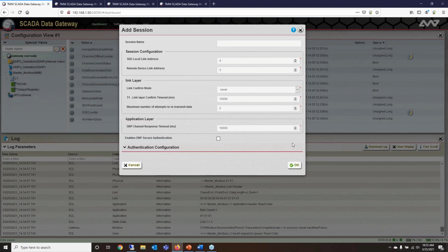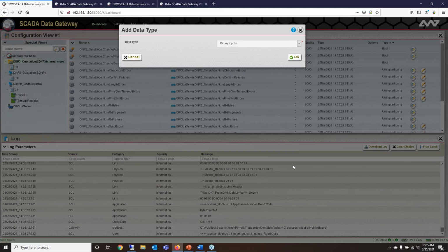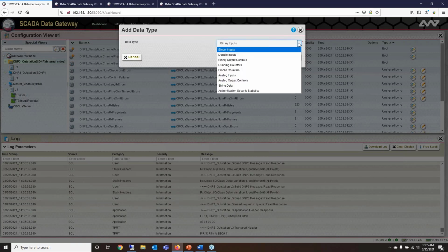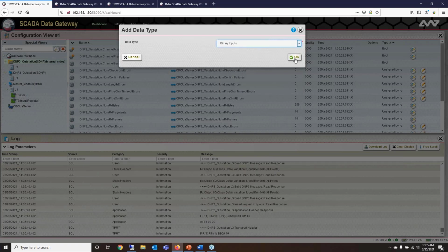And hit OK. You will see this looks a little bit different, and that's because we have chosen a DNP3 device this time rather than a Modbus. That being said, we still filled it with the defaults, and since my control center is also using the defaults, I don't have to swap anything here. So I'll just hit OK. And following the same logic as before, we need to give it a data type. These are obviously going to be different as well because we are in DNP3, but the comparable data type to the coil would be your binary input. So I'll hit OK.